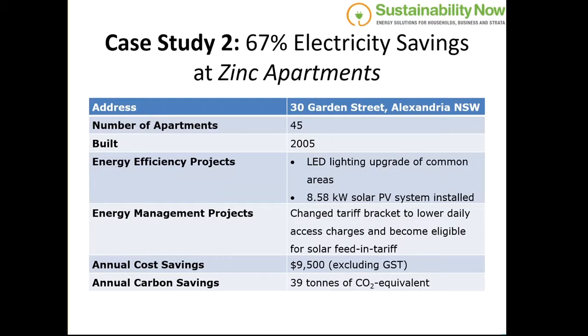Zinc apartments - this one, they've done lots and lots of things. They've upgraded all their lighting to LED, and they went above and beyond. These guys actually put in a solar system bigger than they needed, and they export to the grid 9 months of the year. They're on a tariff rate that supports feed-in, so they get 12.5 cents a kilowatt hour back for what they put into the grid. I think the installer was offering a bigger system for no extra money, so they thought, why not, we'll just do it - we'll subsidise our neighbours' consumption.